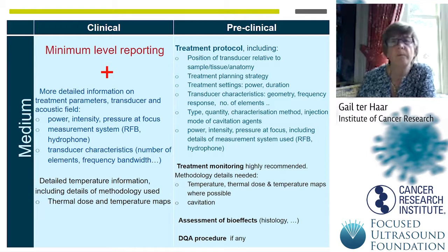Preclinically, this category requires all of that, but we're adding that we want more details about the methodology, about the temperature mapping, how it's achieved, and the cavitation. And we'd like to see some details about how bioeffects are being assessed, so what histological techniques are being used, and so on. And if there's a quality assurance procedure, we'd like to know what that is.